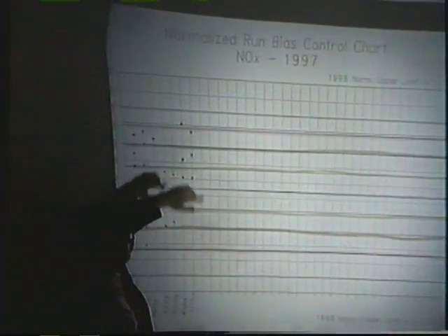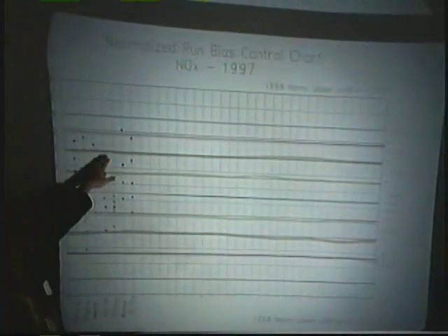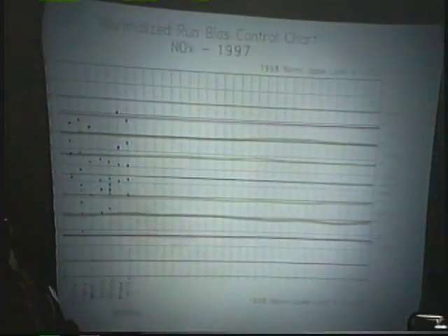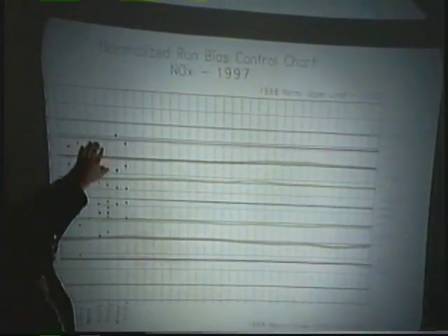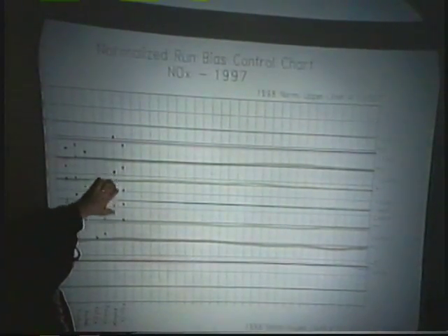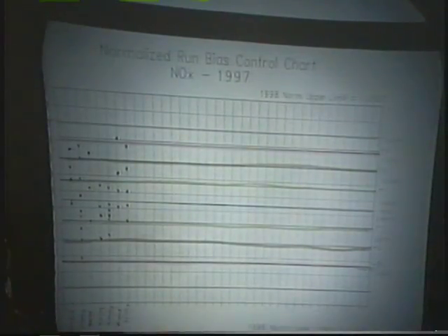Now, this is normalized. One thing that they do is look at the range it's in. If there were 2 samples in a very high range of the analysis, getting up into that deviation from linearity in the regression, they may have just repeated the data that was in there. These other 3 points that are in control down here may have been in the lower range, where the accuracy was good in that part of the run.